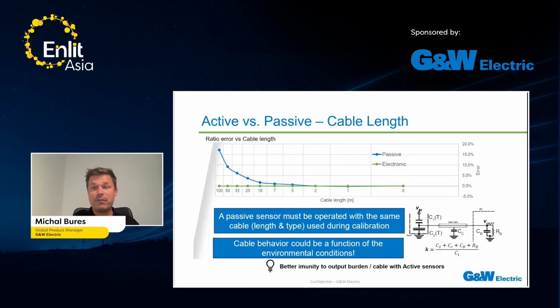Another aspect which is very important for the customer is cable length. With a passive sensor, you usually have a limitation. The secondary cable is usually up to 10 meters. But with active, it's a completely different world. You can go even up to 100 meters and the accuracy is still there. It is still the same, as we can see in the chart. Thanks to the electronics, the sensor is also immune to changes of the burden, which can happen in the secondary cable with some additional capacitance, if some terminal box is connected or whatever. It can make a mess of the accuracy, of course.